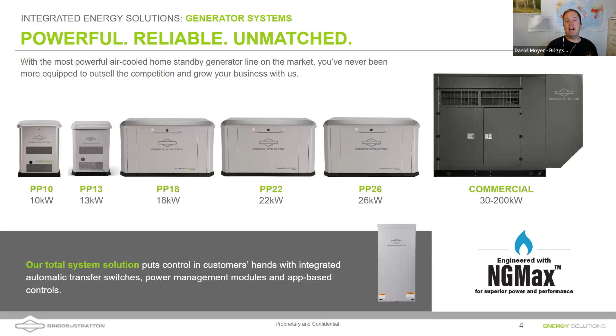One of the most common whole home backup systems in the country really are these standby generators. Like I mentioned, they all use an automatic transfer switch. The generator will detect when the loss of utility occurs, start itself up, and the transfer switch—which is in the center of the screen in that diagram—will recognize the loss of grid and the presence of generator, then transfer over.